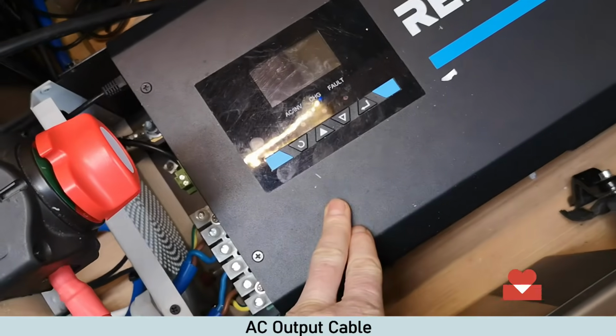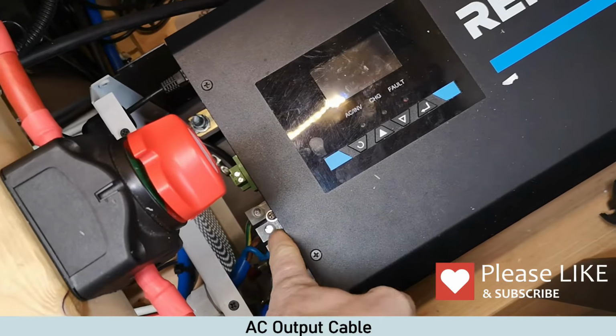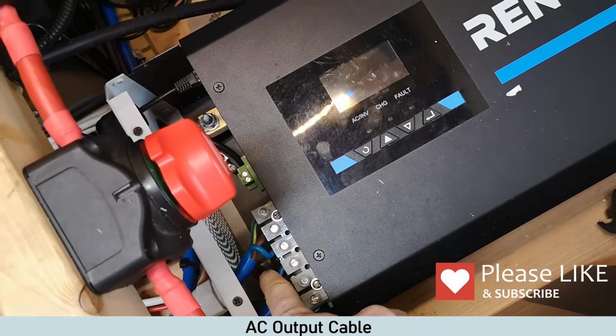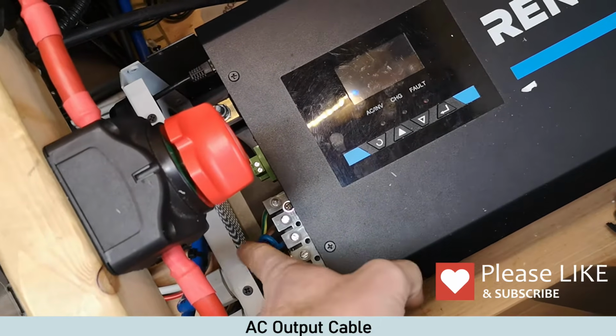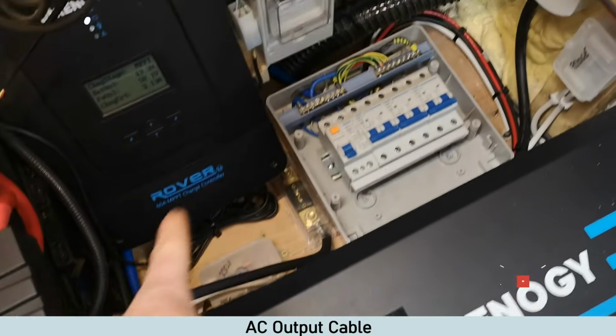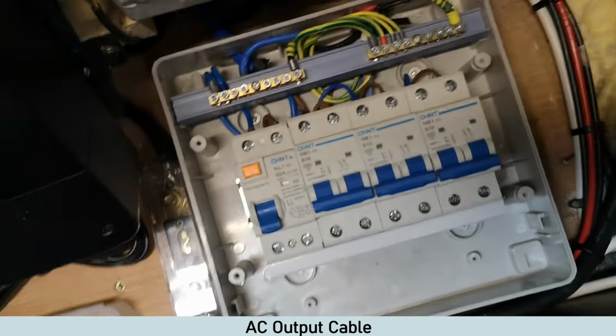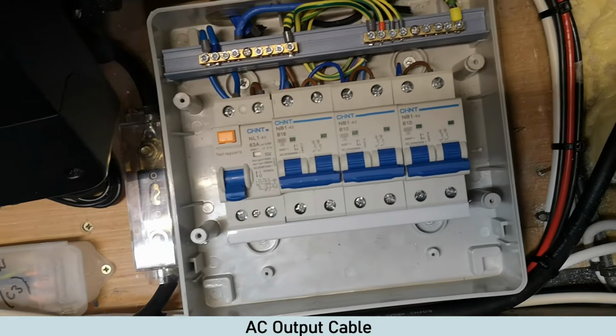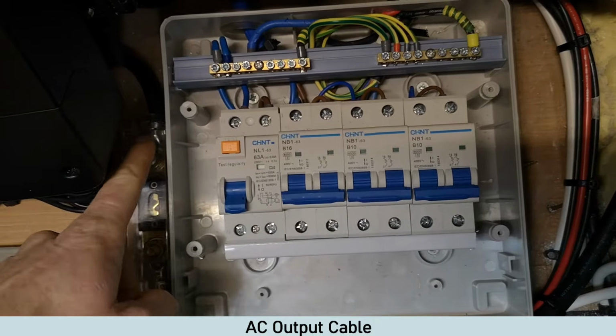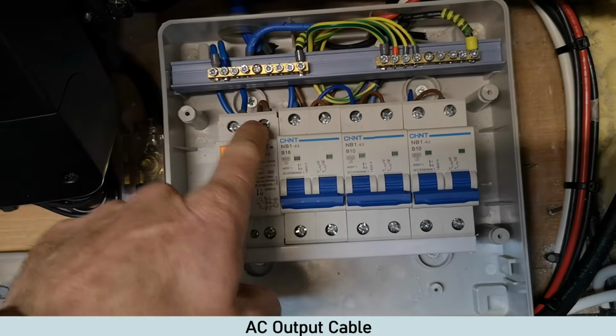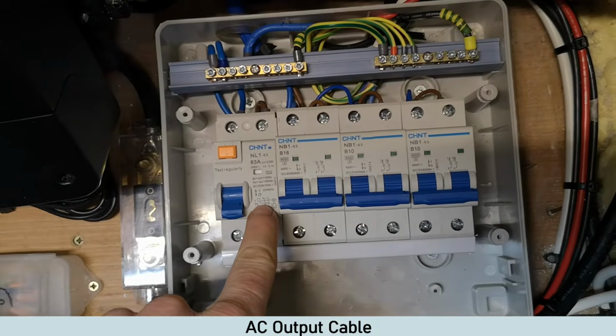So then from the inverter, the AC output, which is these three here, we've used the same cable, 6mm twin and earth again, and that runs out, you can see it there, and it runs into DB2, we'll call it. So what we have here, the AC output comes into the fuseboard, we've got it coming in at the top, and it comes into here, into another RCD.